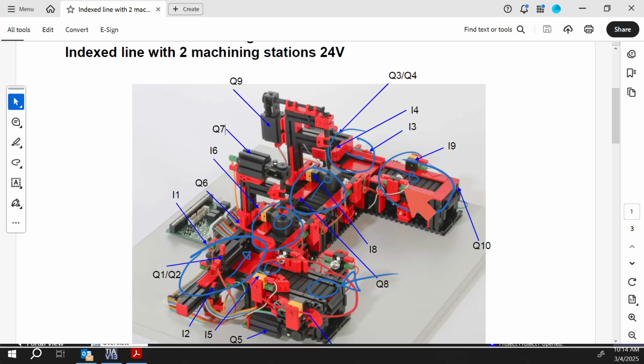The real purpose of function blocks is to be able to reuse your code multiple times. So you can write it once and it can do the same thing 5, 6, 8 times, however many times you have the purpose for that. So if you had 12 of the exact same assembly line lined up, with little sections like this, you could use the same function block code for the first 6 sections on all of them. You wouldn't have to rewrite it 6 times and change all the inputs and everything.